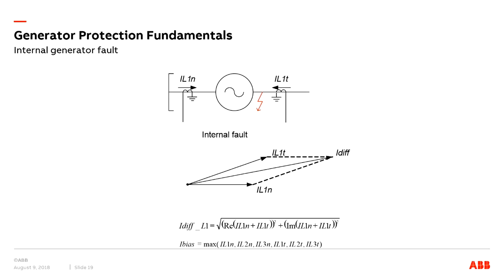So here is how the scheme operates, the differential protection. We have two sets of CTs, one set on the terminal side and the other one on the neutral side, and these CTs are connected to the protection relay. So for an internal fault, the differential current will be the vectorial sum of the neutral side generator current and the terminal side generator current. And there is a bias current, or the restraint current. It will be the largest phase current on the neutral side and the terminal side.